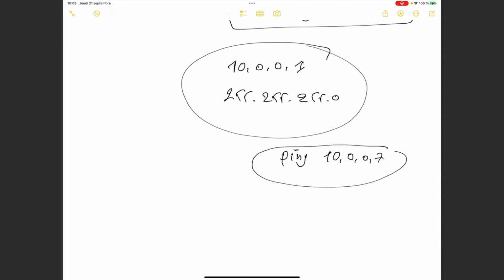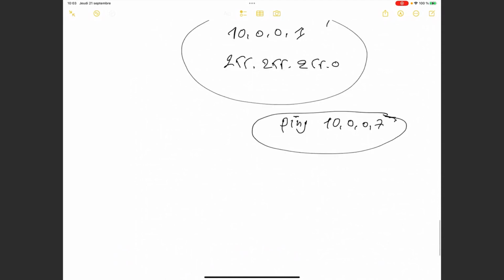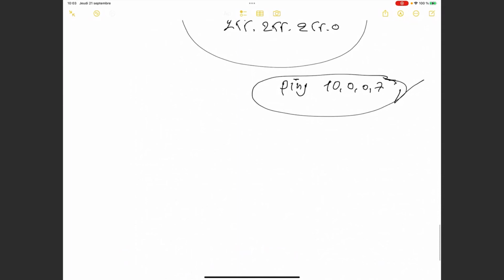If the instrument replies normally, but the operation software installed in the computer doesn't recognize the analyzer, or it says no communication, it means that there is a mistake in the setup file. So you go to the installation folder of the analyzer, to D, and check the setup.ini file. Make sure that the IP address of the analyzer is 10.0.0.7, because it is the setup.ini file that tells the software on the computer where to find the analyzer, which address. All right. Okay, let me go back to the PPT.